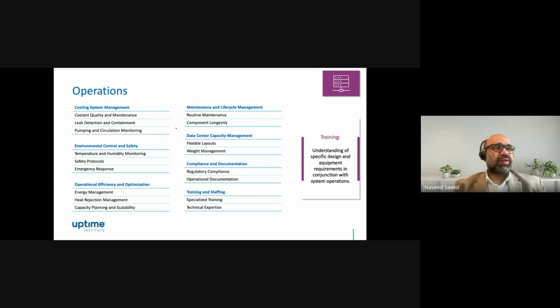attribute here. Environment control and safety. What are the temperature and humidity requirements? Do we need stricter control or not? How is it going to impact the liquid that you have selected? What are the do's and don'ts in that case? Safety protocol: if the liquid spills over, what is to be done, where can it be drained? Different geographies and legislations have different requirements for that. So, for example, in the United States, in some of the states, you cannot drain glycol water into the regular drain of the building. So you have to contain it separately. So there has to be a separate piping system that has tanks that can collect all that liquid, and then the vendors can take it offsite. So that's really important. Emergency response, all these things need to be thought about. Operational efficiency and optimization.